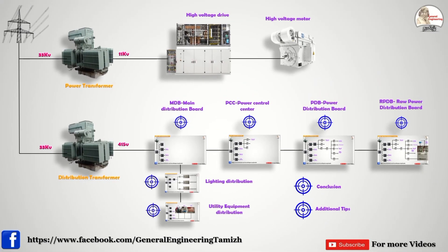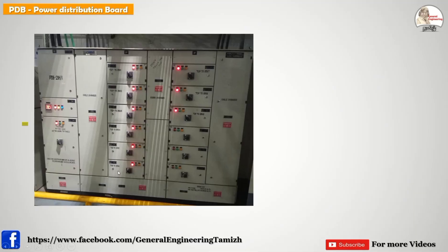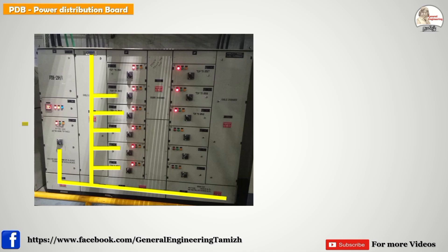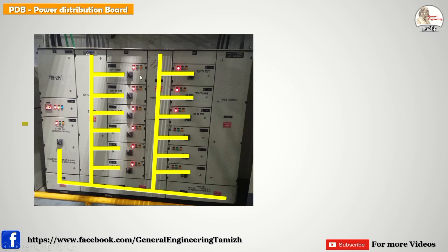Now PDB is completed. The PDB panel looks similar to the PCC but the panel size is smaller. The incomer breaker supply comes from the PCC. Across the PDB, power distribution is done the same way — from the incomer breaker, all outgoing feeders are connected through the bus bar. The key difference is that the breaker rating is smaller because the connected load rating is also smaller. From the outgoing feeder, RPDB and welding circuits are connected, with names labeled on the panel.